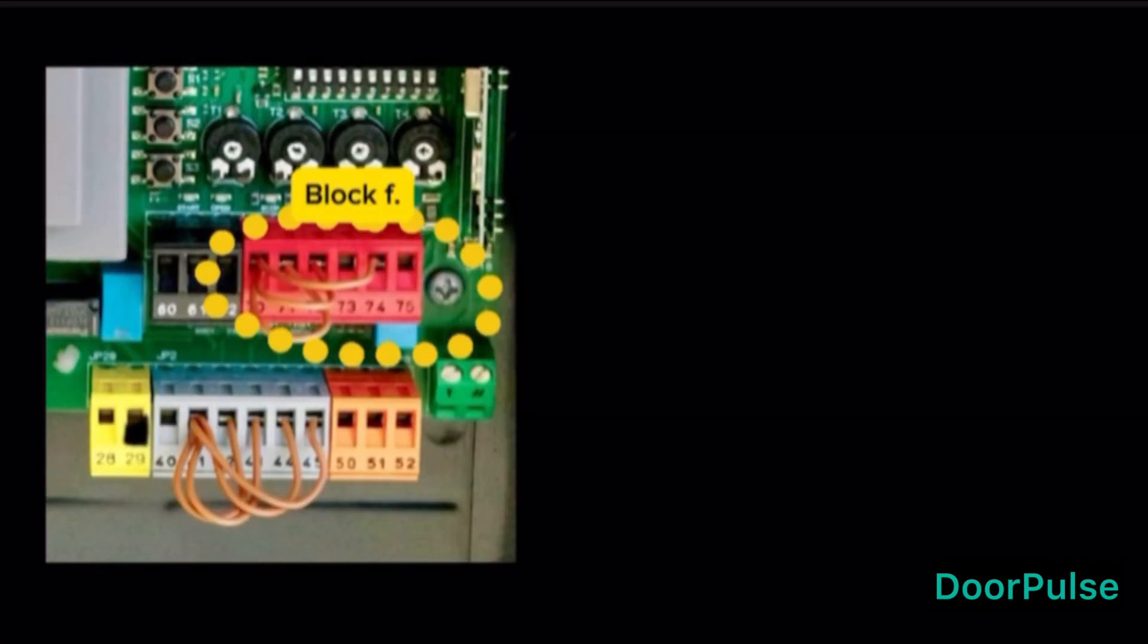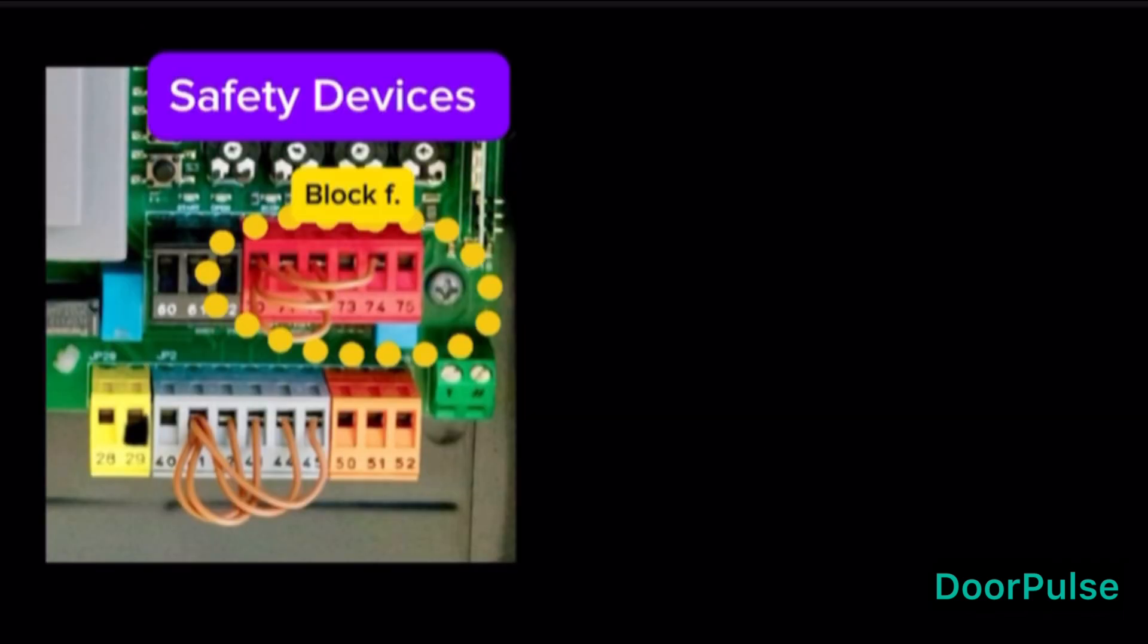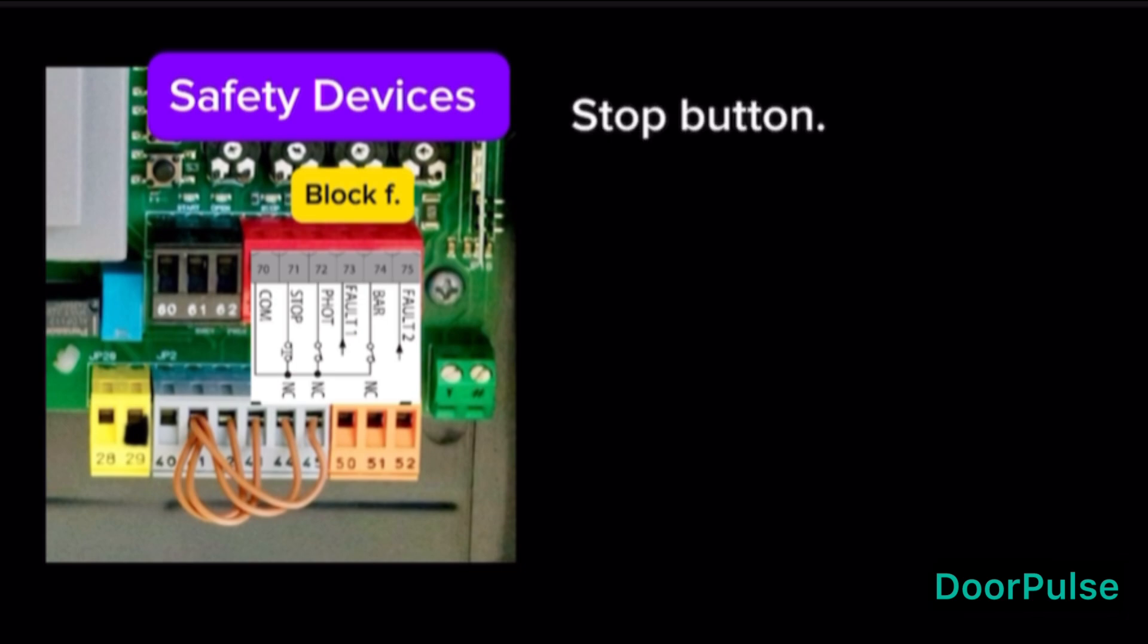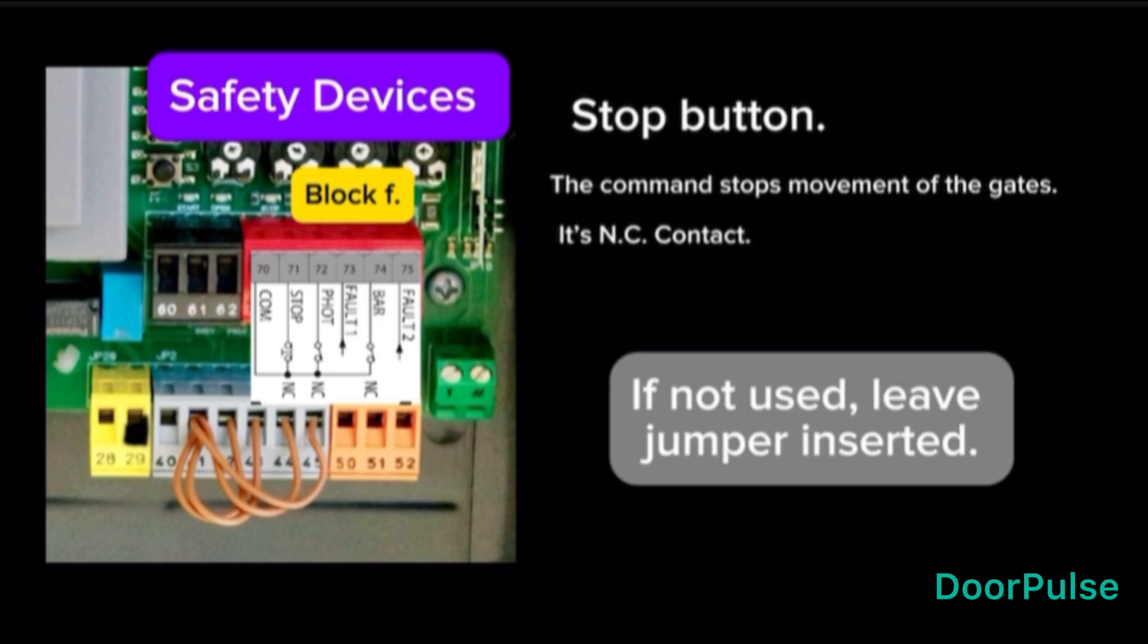Block F, Safety Devices Block. Terminal 70 is common for this safety devices like stop, photo, and bar inputs. Terminal 71, stop button. The command stops movement of the gates. It's NC contact. If not used, leave jumper inserted.